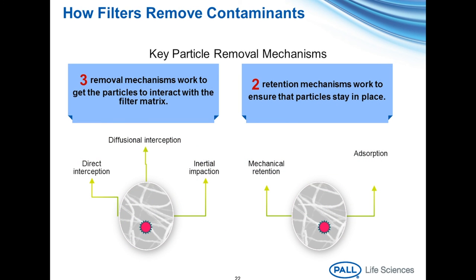There are three removal mechanisms that work to get particles to interact with a filter matrix. The first is direct interception: the removal of a contaminant or particle via physical size. If contaminants or particles are too large to pass through the filtration matrix, they are retained in or on the matrix. The second removal mechanism is diffusional interception: the removal of a contaminant or particle due to random motion as that particle passes through a filter matrix. This is primarily used to describe the filtration retention mechanism of gas filters when used to filter gas.